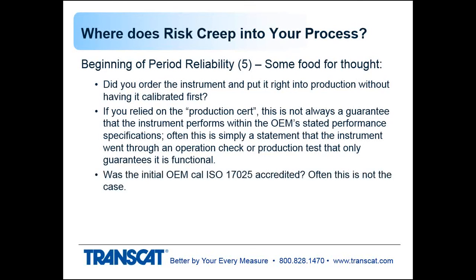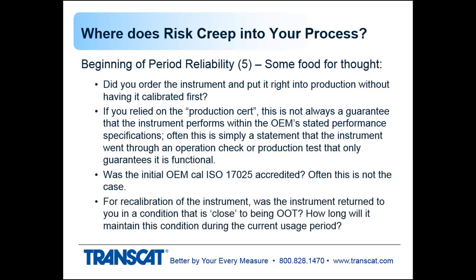Was the initial OEM cal accredited through 17025? Very often this is not the case. And there are other errors that can be introduced that are not accounted for in the calibration. And then for recalibration of an instrument, not the new cal but subsequent cals, was the instrument returned to you in a condition that's close to being out of tolerance? Did it come back from the lab with some of the readings very close to the tolerance limit, meaning that in the next calibration interval, it has a chance of going outside of those acceptable limits? And what would that do to your decisions about product or wherever the instrument is used?